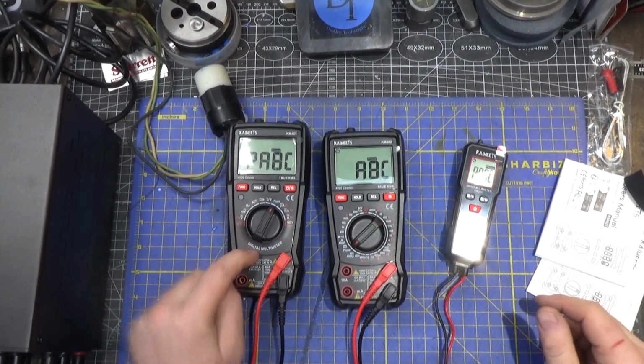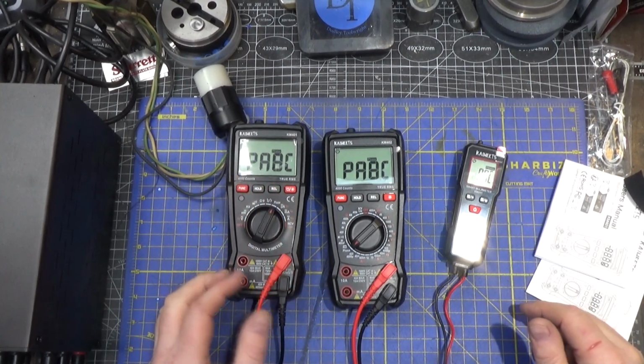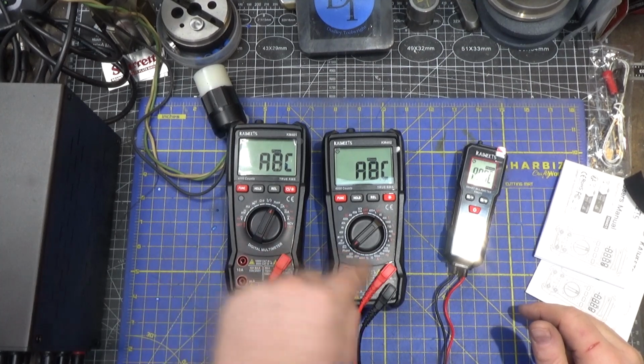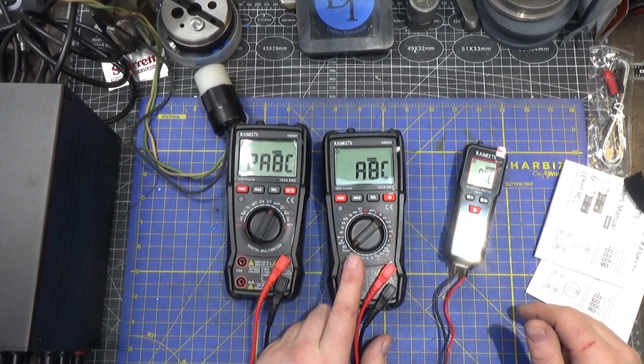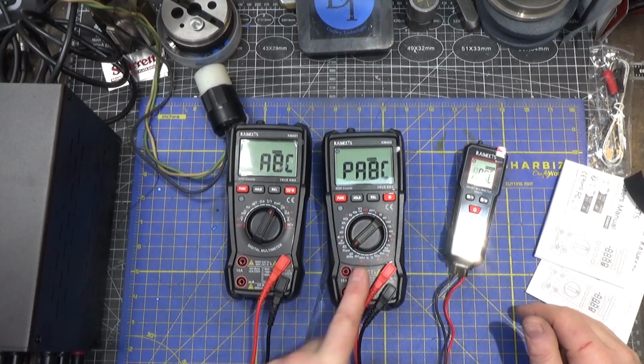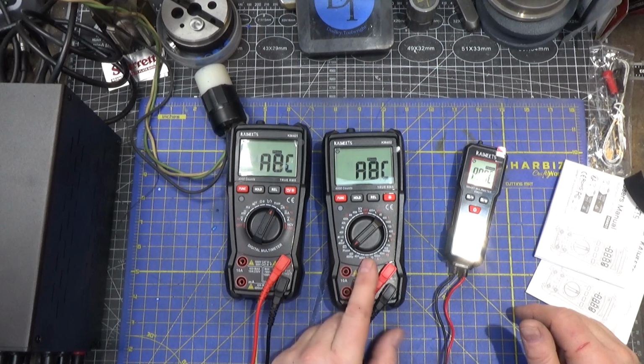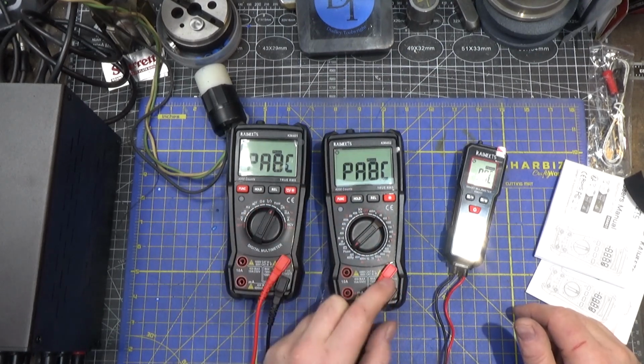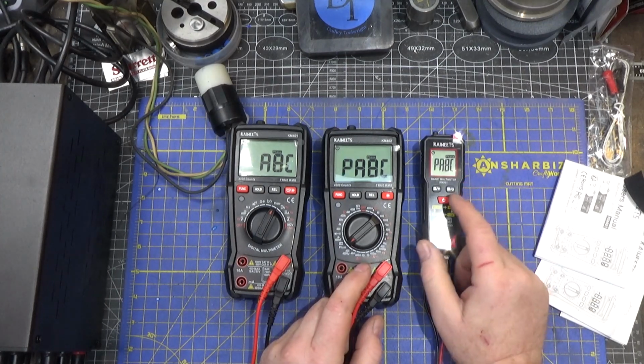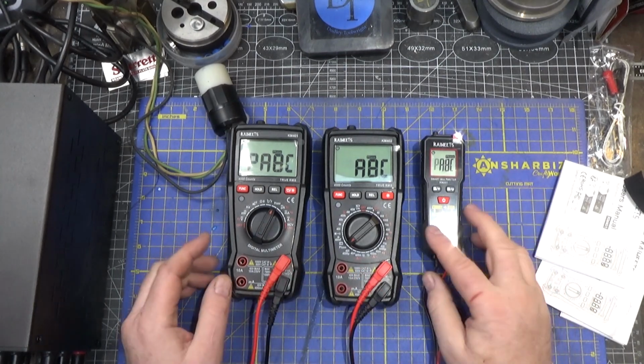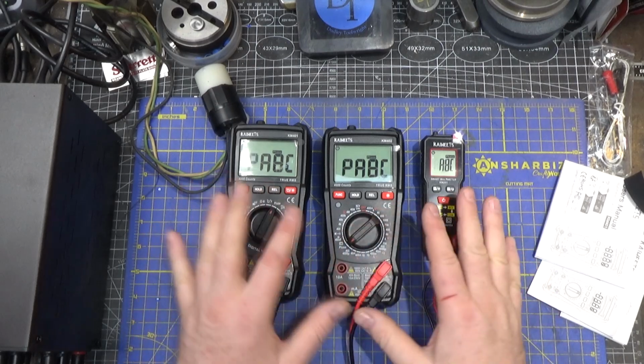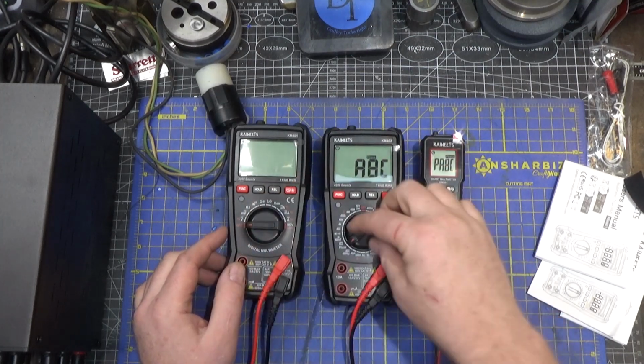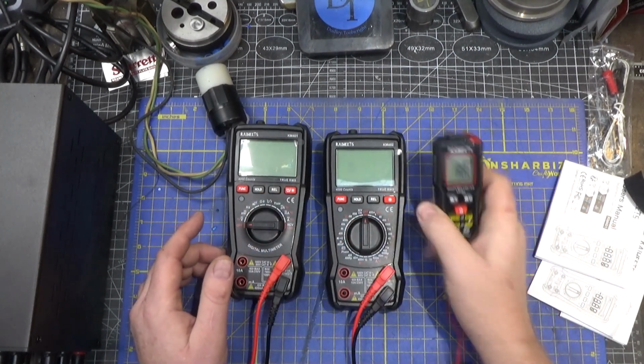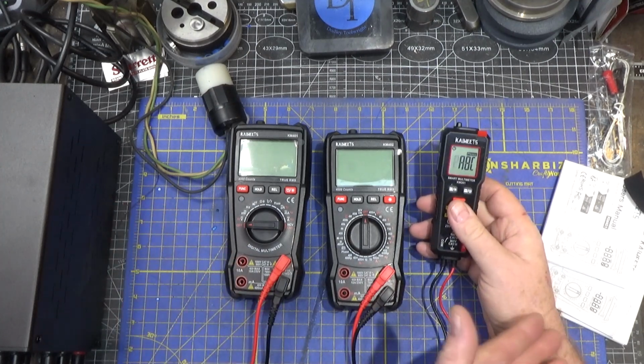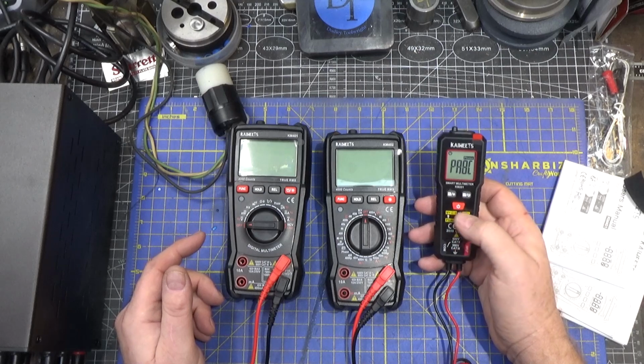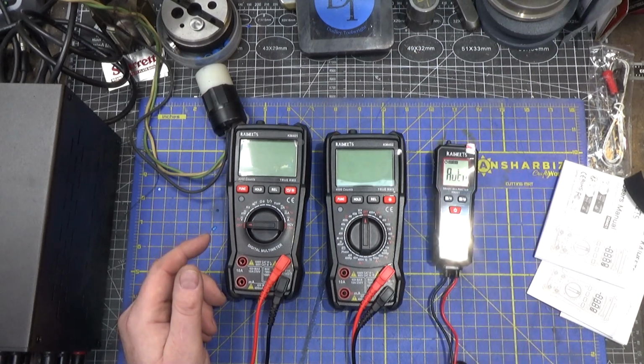So for the phase measurement, this one I really couldn't get to work again, even with the lathe running—a 5 horsepower motor turning at high speed. This guy did work the first time, struggled a little bit the second time, and struggled again the third time, but I was able to get the first two, and the third I couldn't complete at all. I was trying to do the phases out of order to see if I could get it to go the other direction. This one got a couple of the phases and then couldn't detect the third phase at all. Don't really know why they're having so many issues with it, but bottom line is I think this particular feature of the meters is not really ready yet, or there's something I don't know. I'm following the instructions in the manual and they're not giving me any hints about anything else I should do, but I don't think it's working too well.